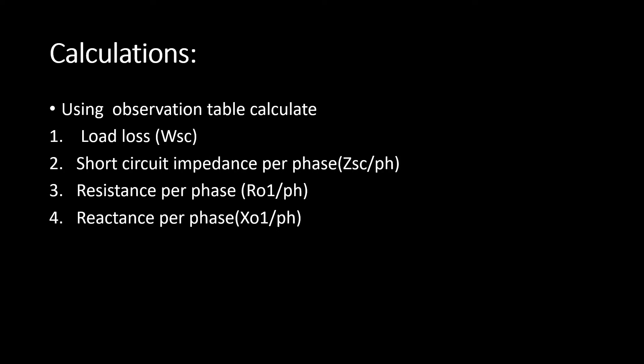Now for calculations: all data has been entered in the observation table, so we are in a position to calculate load losses, short circuit impedance per phase, resistance per phase referred to primary side (R01 per phase), and reactance per phase of the primary winding (X01).